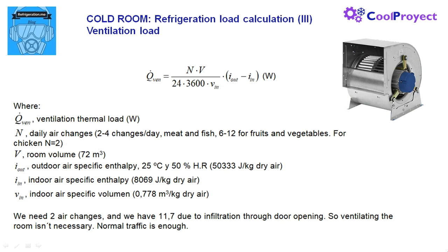In this case for chicken fillets we need around 2 changes per day. Since we need 2 air changes and due to infiltration we have 11.7, then ventilating isn't necessary for our cold room. The normal traffic air infiltration is enough. If it weren't good enough we should install a ventilation system and take into account this additional thermal load.